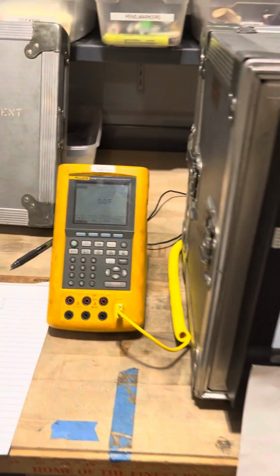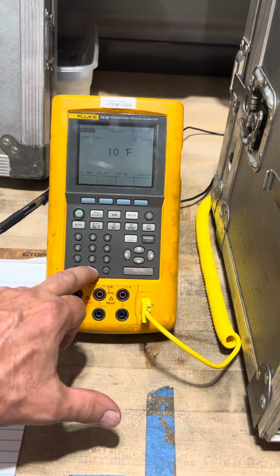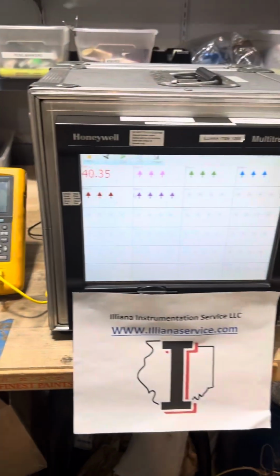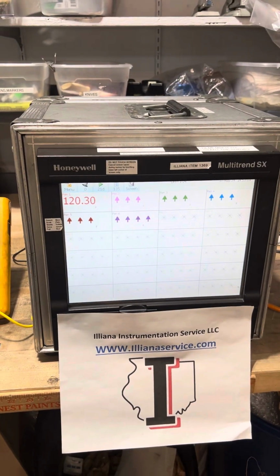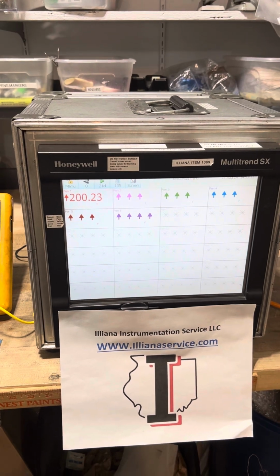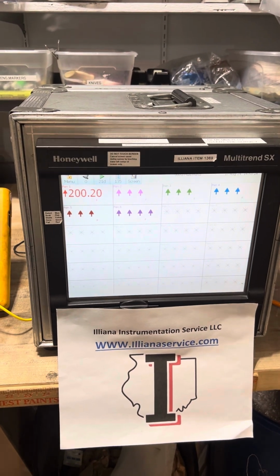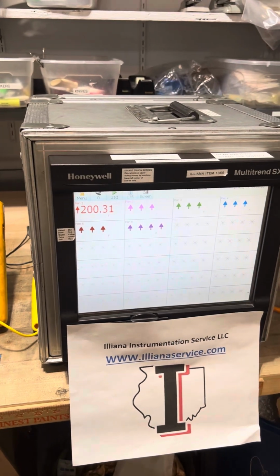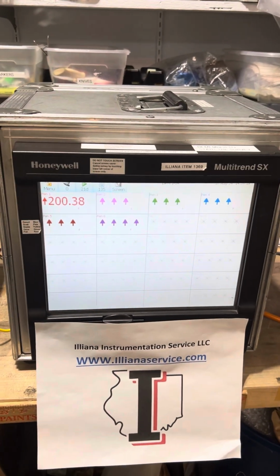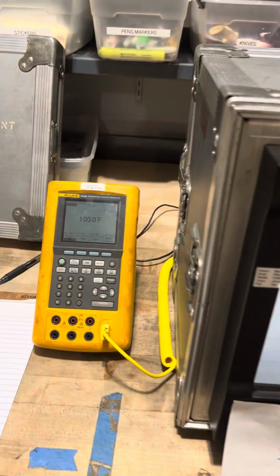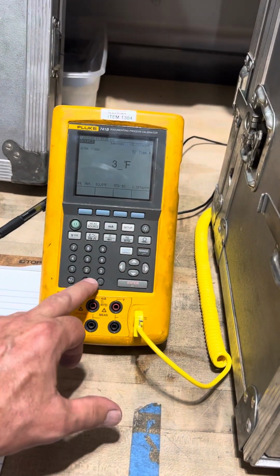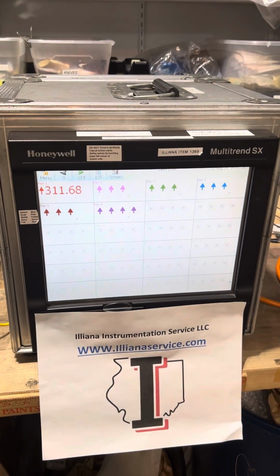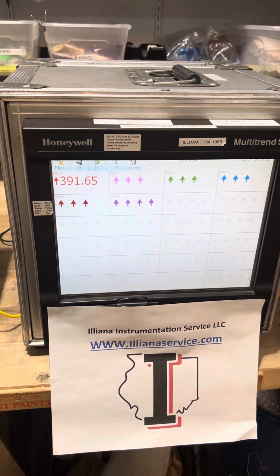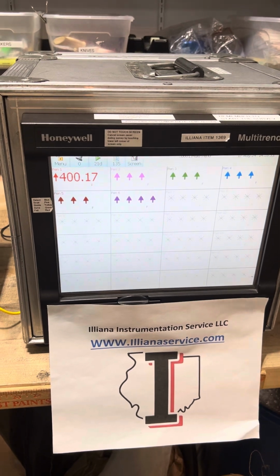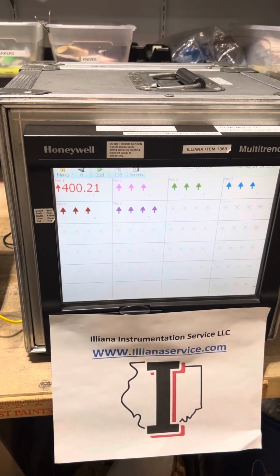If I put 100 into the calibration source right now, you'll recall that our offset was 100, and the recorder is going to take the 100 that it should read, and it's going to add the 100 offset into there, and it's going to in fact read 200. And that's going to be the case everywhere from 200 degrees on all the way up to 600 degrees. So if I were to put 300 here, it's going to go ahead and add that 100, and it's going to read 400 degrees. So this is a method of calibrating the recorder.